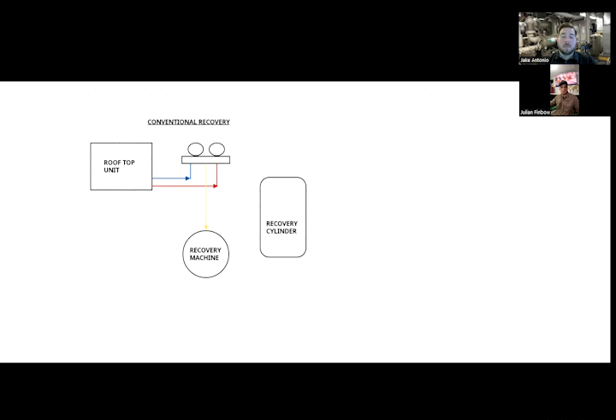Some of them handle liquid very well, some of them at a different rate. So it just depends on the style and the brand. But that's when you've got to pull the manual out and understand your own equipment. The recovery machine is basically going to pump the refrigerant for you. That's kind of the design behind it. So out of the recovery machine, we're going to go into our recovery cylinder.